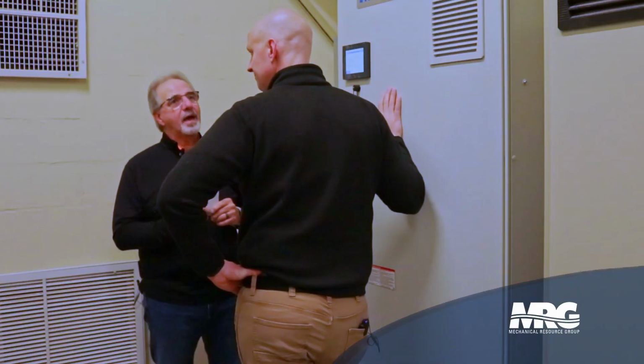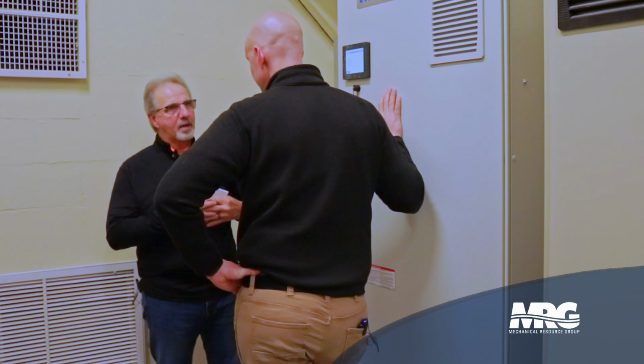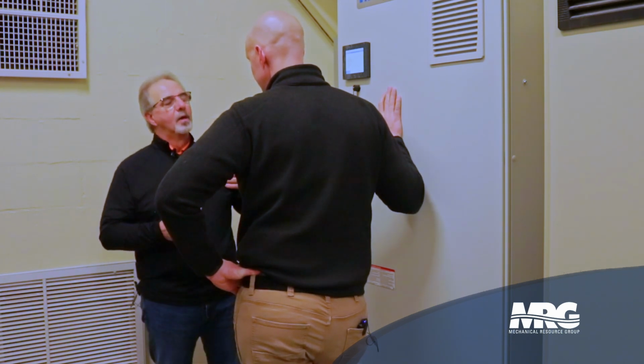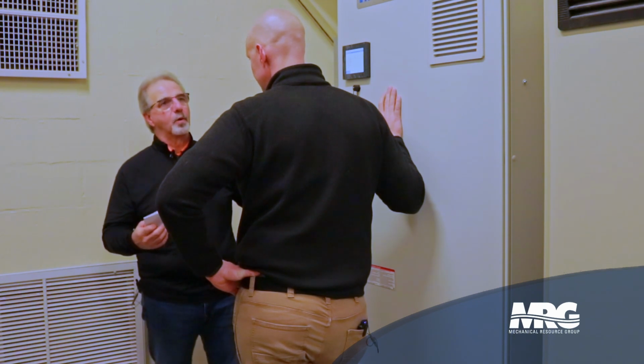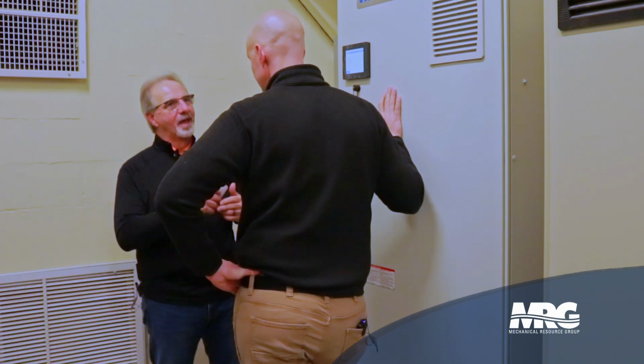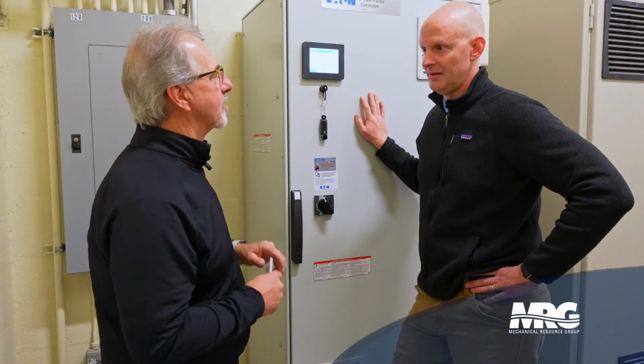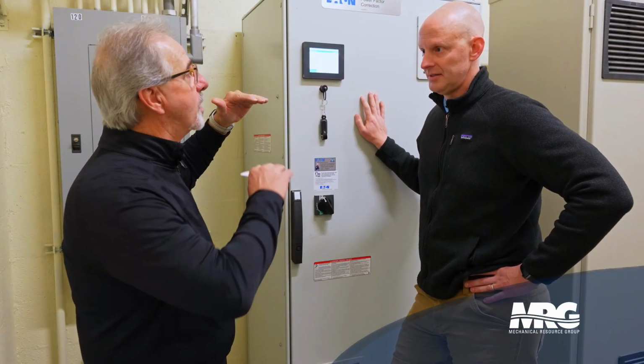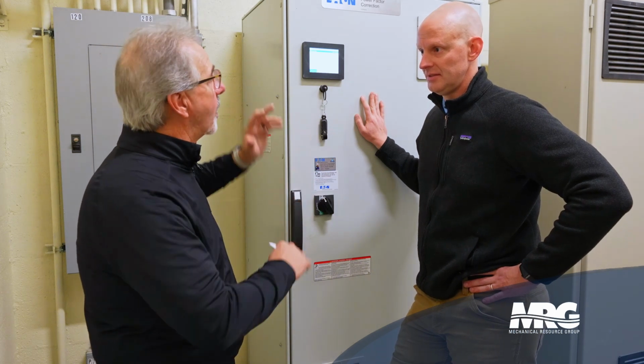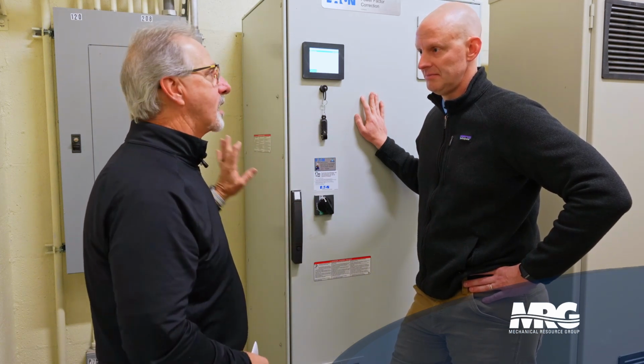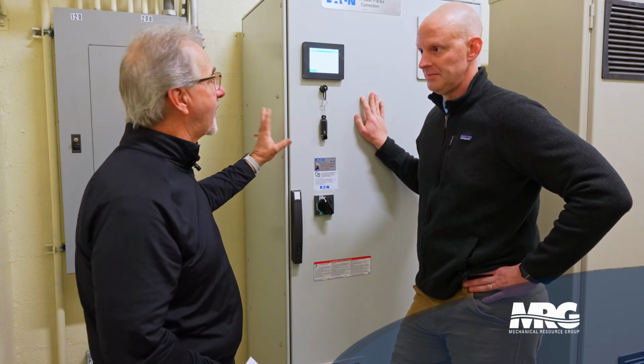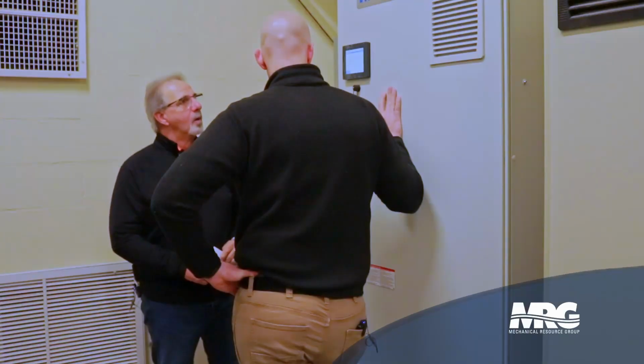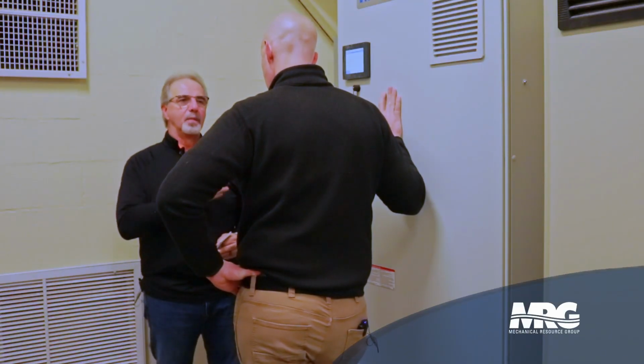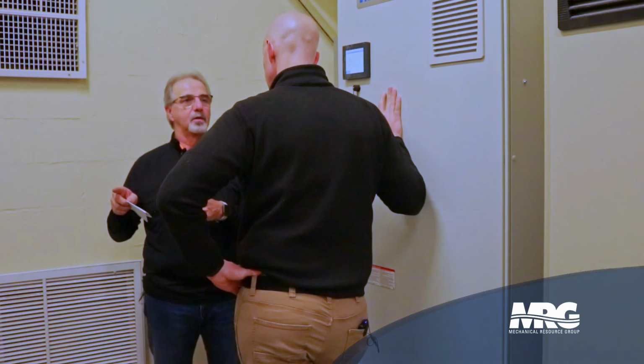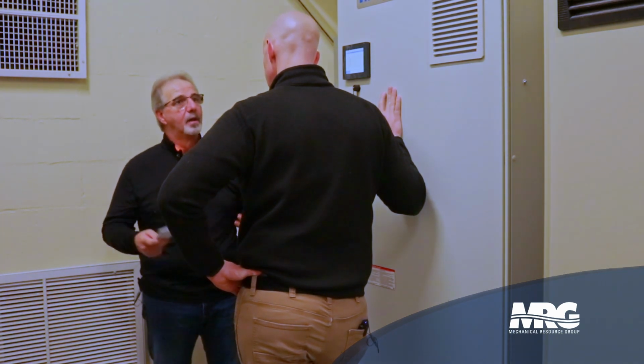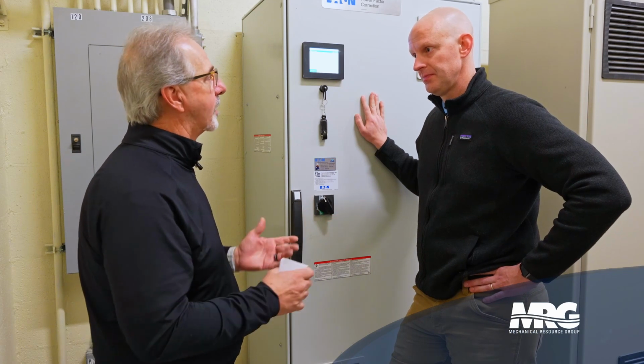Right. And the reason why you have that is because, believe it or not, there's a substantial amount of single phase load here. We're pulling that load, it's about 40 amps worth, off of legs 2 and 3. And that's why the current is low on number 1, because our voltage is much higher than the other 2 legs. So the lower the voltage, the higher the current. But we also had to protect that single phase load, so that's why we had to incorporate it into the filter. As they go along, they have constant metering of this device as well, just like they do the drives. They can come in and get real-time data as much as they want to, and they do trend these pumps, so they do get an idea.